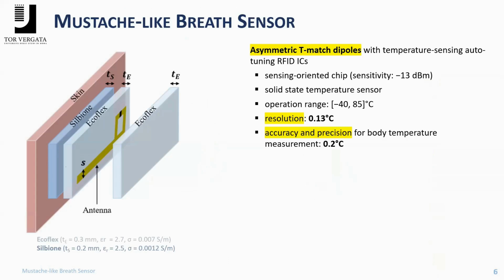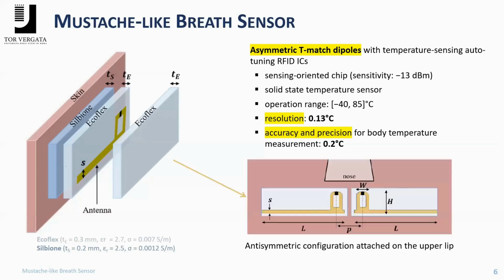In particular, we use two different kinds of elastomers. The antenna is between Ecoflex, and then Silbione, which is very sticky for application on the skin. Ecoflex is less sticky, so it's more suitable for the antenna. Here there is the sensor that is capable of performing a temperature measurement with a resolution and accuracy that are, we can say, suitable for monitoring the small gradient that we have close to the nose. Then we have to pack two of these, so that the sensors will be put very close to the nostrils and can collect nearly independently the airflow temperature.